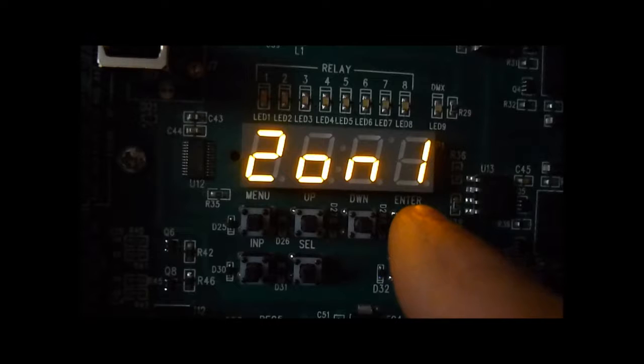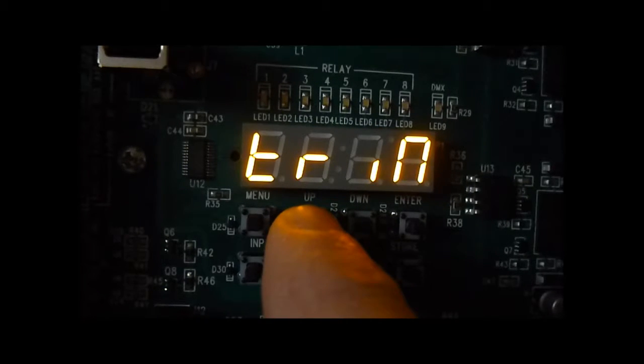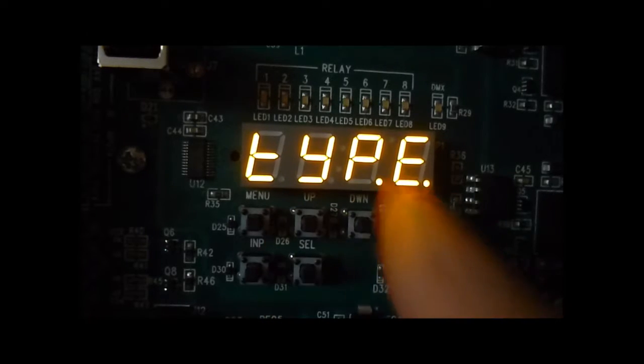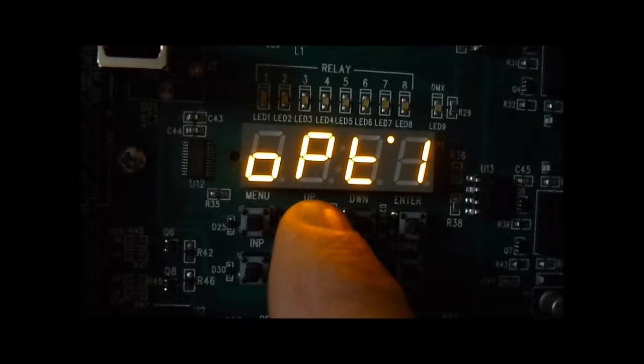Press enter. There are several options here for each zone you set up: the type and the trim. There's a high and low trim. We'll go to type and there are three options. Option 1 is 0 to 10 volt dimming, which is the default. Option 2 is switched, and option 3 is receptacle mode.